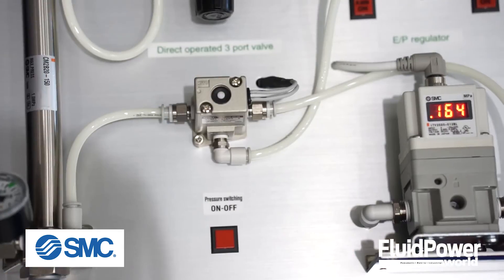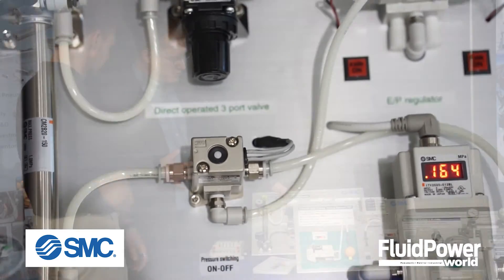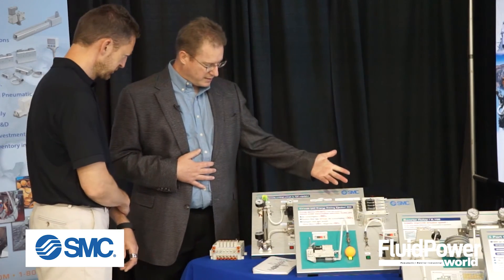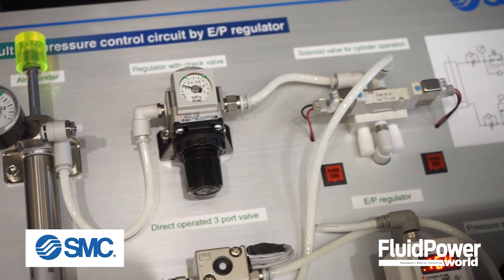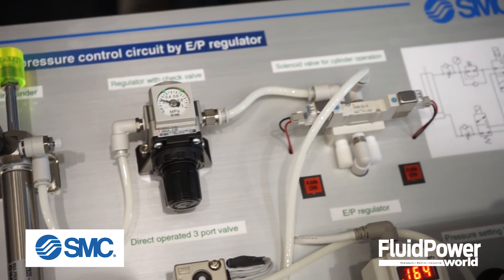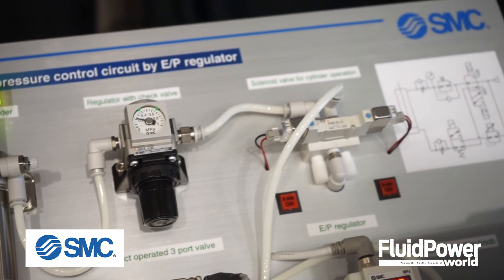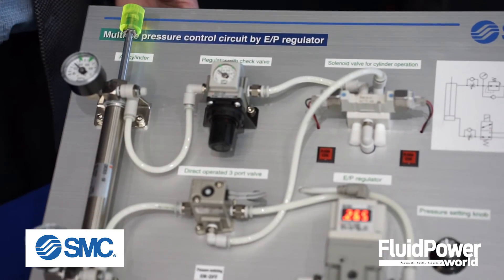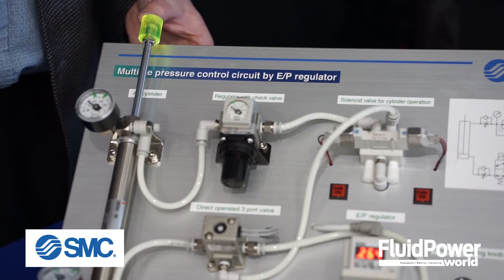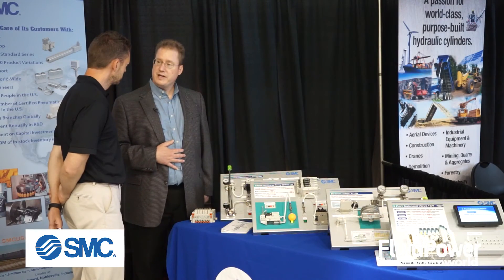As well, in web converting — that's popular here in Wisconsin — we're also showing some of the similar I/P and E/P regulator technology that's available for creating those dancer-type applications for web processing. These are precision regulators, electronically controlled, that have a high response time on exhaust so that you can quickly react to those pressure demands.